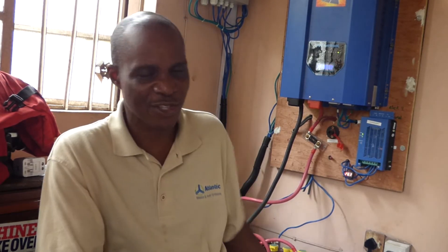How long does the system last? The panels will last about 25 years — there are panels that have been in the market for longer than that. The batteries, if managed well: sealed lead-acid batteries (dry cell) can last 3 to 5 years. The Trojan flooded lead-acid batteries you see behind me can last as much as 7 years. The industrial (IND) batteries, which are the bigger ones, can last longer than 10 years.